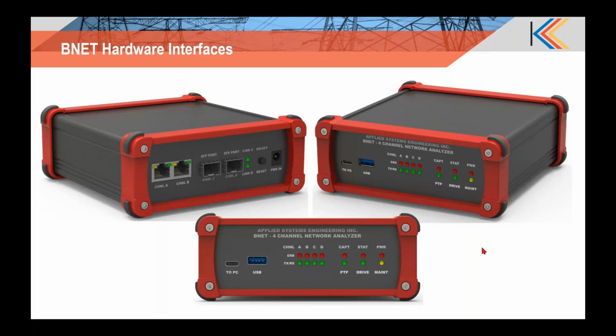For the full simulation, we'll have to depend on the IED Smart tool. ASE61850 IED Smart comes as a simulation tool for the entire substation, and there you will be able to simulate a larger number of IEDs. But we don't have sample value functionality there. It's only GOOSE and MMS capabilities that can be simulated. So sample value can only be done through BNET.